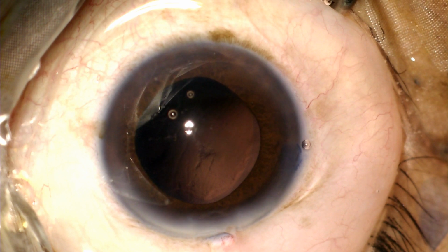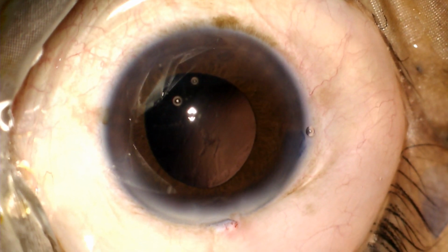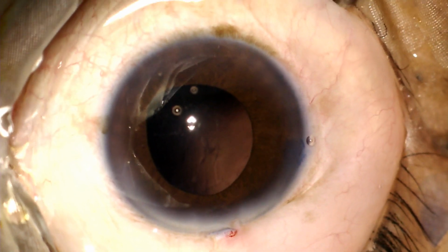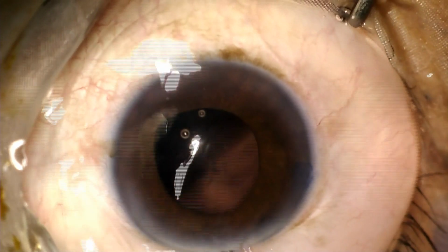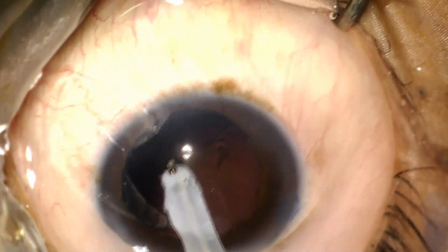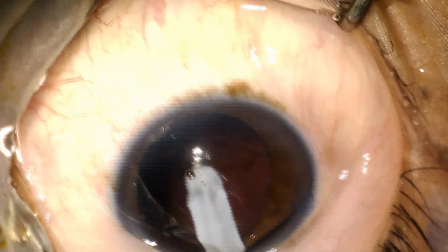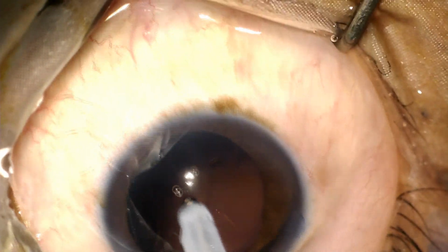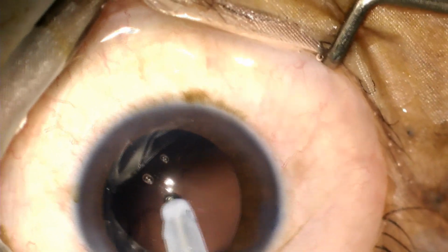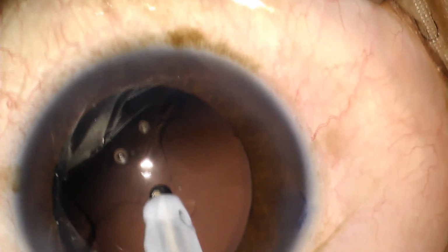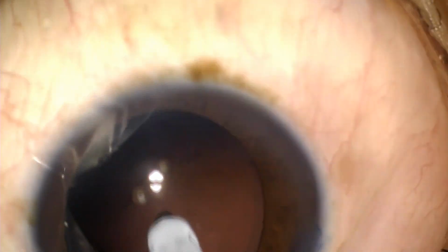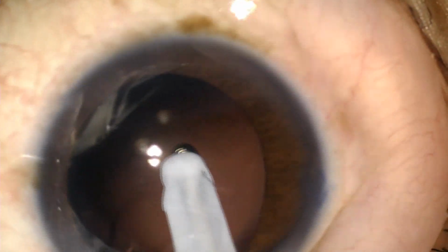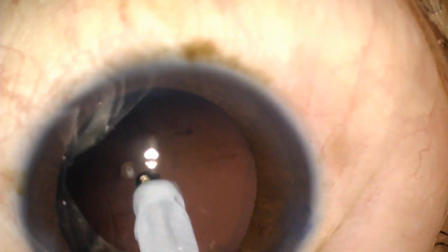So what should we do? Yes, we can proceed with IOL implantation and do a YAG laser posterior capsulotomy after say 3 months or so. But I decide to do a PC polish here. So I go to the polish mode where the vacuum is only 20 and I'm just in position 1 with irrigation. I'm using mechanical force to rub onto PC to see whether the remnant material, the residual material dislodges or not. And then I go to higher magnification, focus again, and then start rubbing it with irrigation only. I'm not giving any aspiration as of now, and I'm doing multiple strokes of rubbing to see whether it detaches or not.